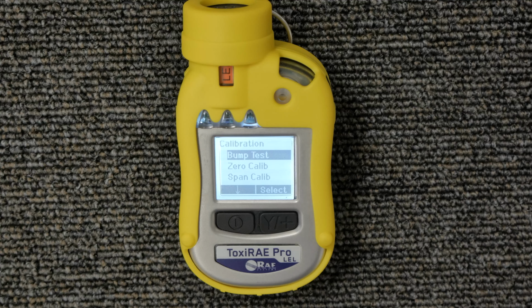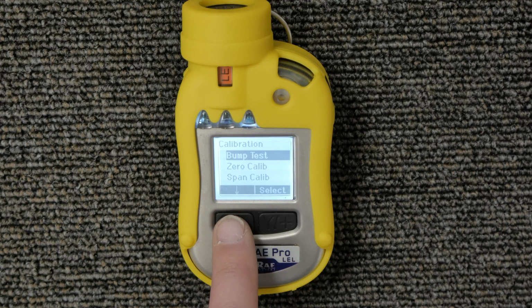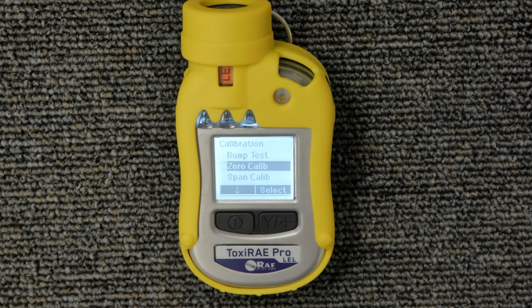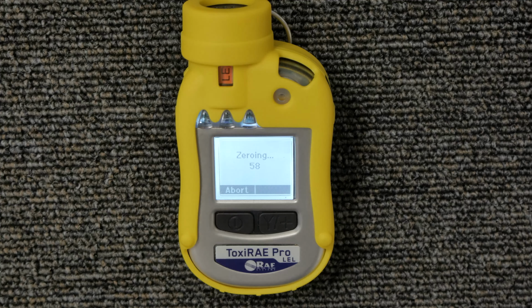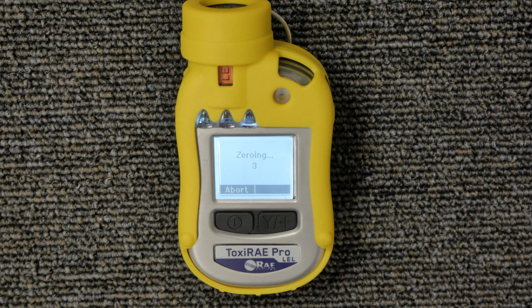Now you're in the calibration menu. You want to scroll down with the power button until the cursor is over 0 calibration, then hit the Y plus button to accept it. And then it says apply 0 gas. That is going to be ambient air in a fresh air environment. So you're going to hit the Y plus button.